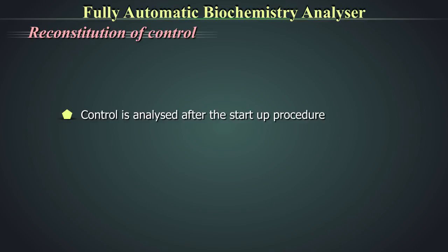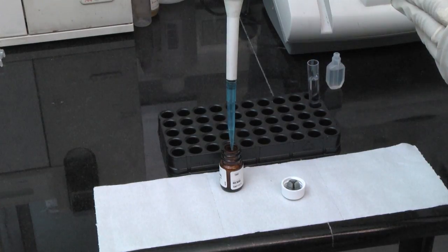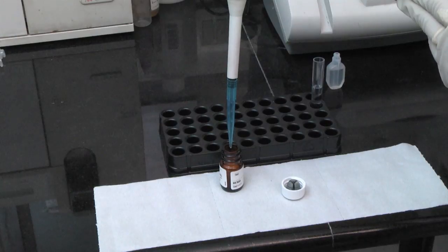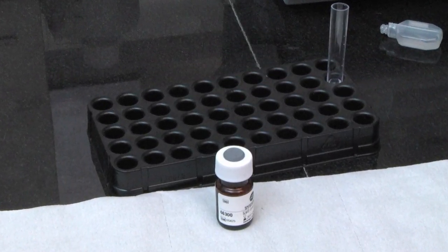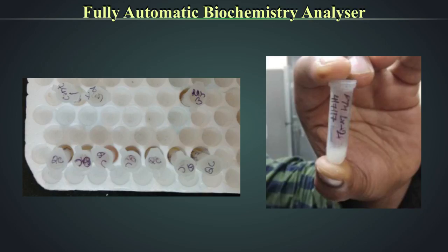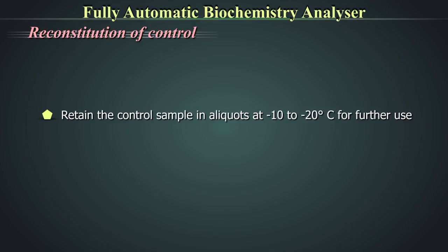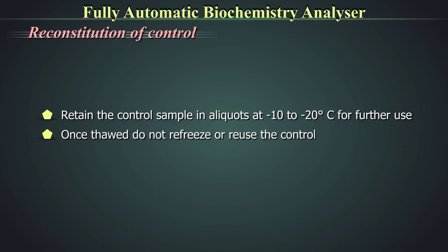Reconstitution of control: The control sample is analyzed after the start-up procedure. Controls are in lyophilized form and reconstituted before use. Using a calibrated volumetric pipette, reconstitute the control with 5 ml of commercially available deionized water. Allow the control to stand for 30 minutes at room temperature, swirling intermittently. Prepare aliquots as per requirement and label them with lot number and date of expiry. For testing, take out a single vial, mix several times to ensure homogeneity, and remove the stopper before sampling. Retain control samples in aliquots at −10 to −20°C. Once thawed, do not refreeze or reuse the control.